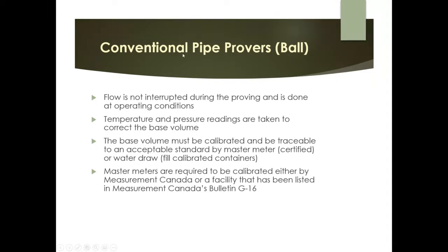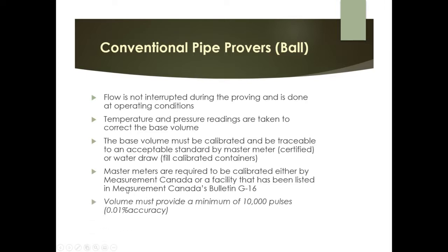The prover volume must provide a minimum of 10,000 pulses — an important number that comes up repeatedly. The reason: more pulses increases resolution, and higher resolution yields better accuracy. Every zero removed from the pulse count shifts the accuracy accordingly. 10,000 pulses is the established minimum standard.